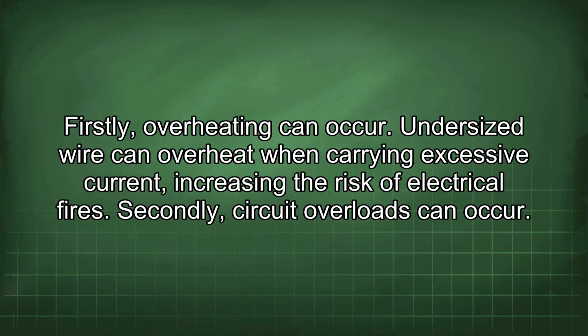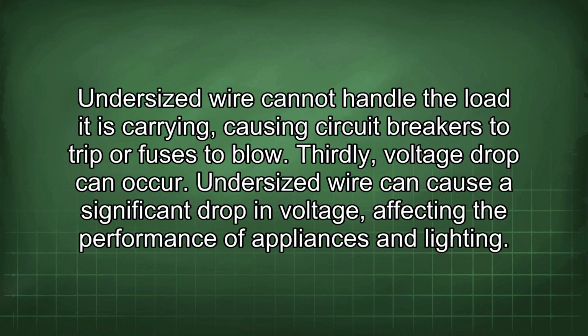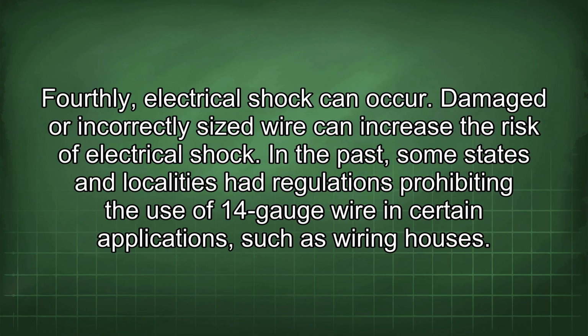Firstly, overheating can occur. Undersized wire can overheat when carrying excessive current, increasing the risk of electrical fires. Secondly, circuit overloads can occur. Undersized wire cannot handle the load it is carrying, causing circuit breakers to trip or fuses to blow. Thirdly, voltage drop can occur. Undersized wire can cause a significant drop in voltage, affecting the performance of appliances and lighting. Fourthly, electrical shock can occur. Damaged or incorrectly sized wire can increase the risk of electrical shock.